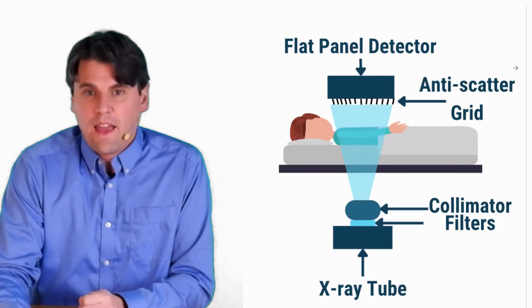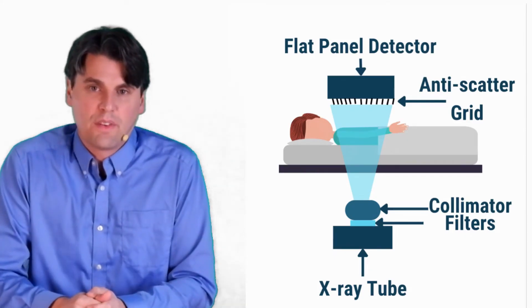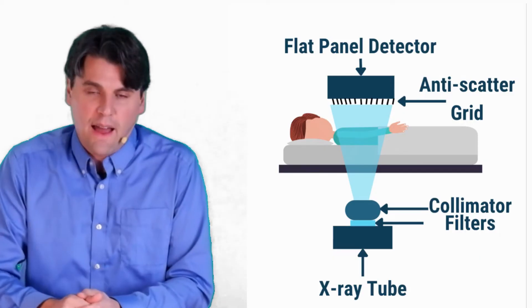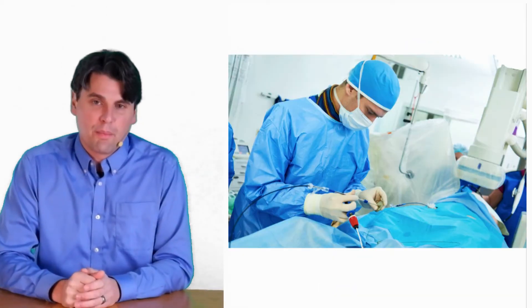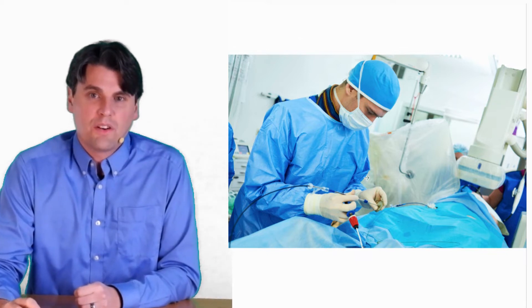And then you have a flat panel detector, which is kind of the state of the art. So most of the systems nowadays are using flat panel detectors. So it looks like in person, if you're actually looking at a percutaneous procedure here.